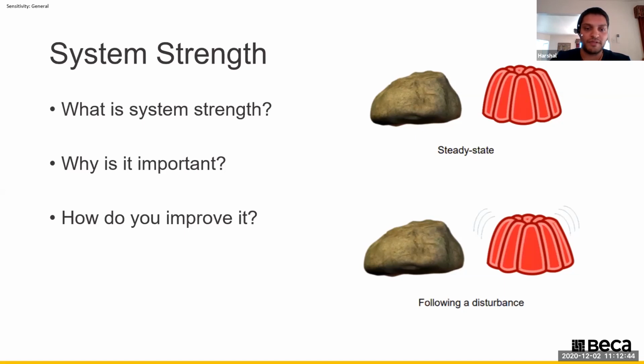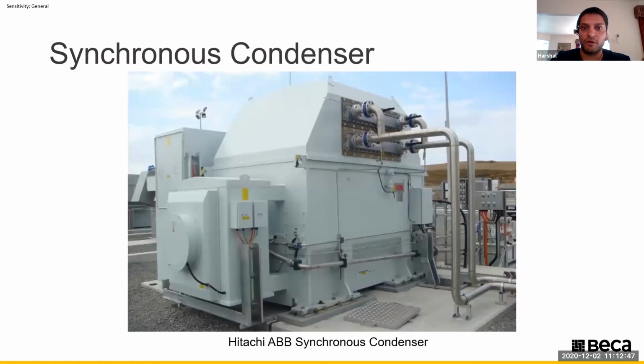So how do we improve system strength? One option is to install a synchronous condenser, which is essentially a synchronous generator that doesn't produce any real power, and is specifically designed to provide reactive power for system strength support in response to network disturbances. This is a common solution amongst developers; however, it comes at a high upfront capital cost, which can actually tank the project before or during the grid connection assessment process.